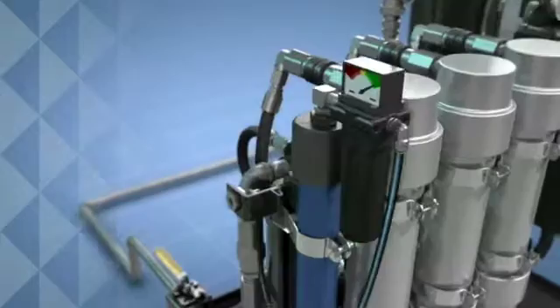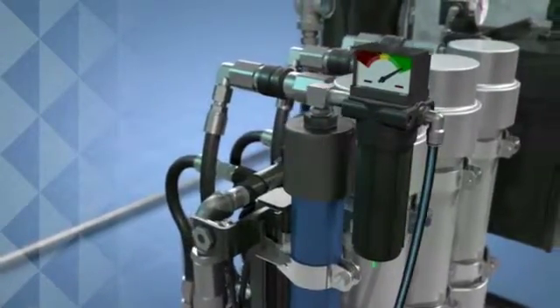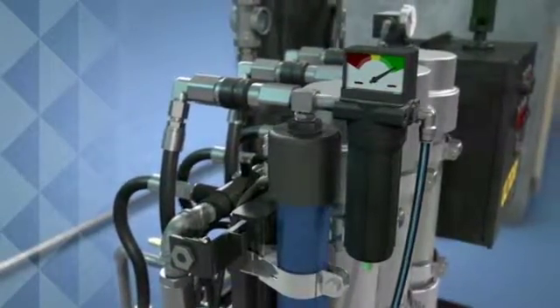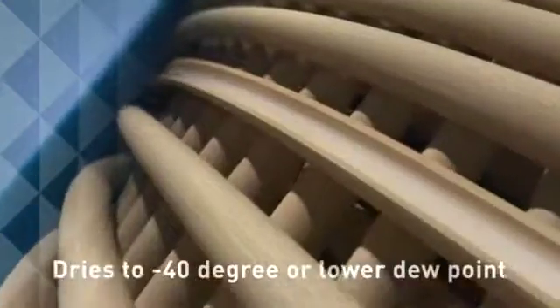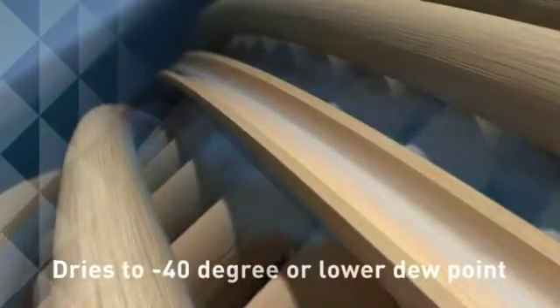Plant air enters the coalescing element to remove liquid, aerosols, water, oil and submicron particulates from the airstream before passing through the membrane air dryer. Here it reaches extremely dry levels of minus forty degree or lower dew point.